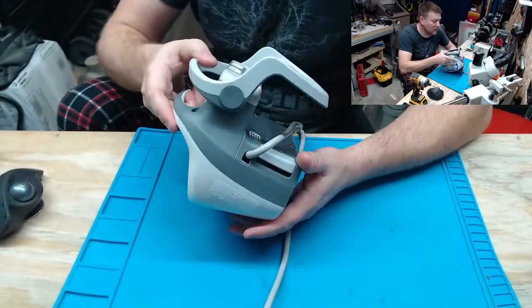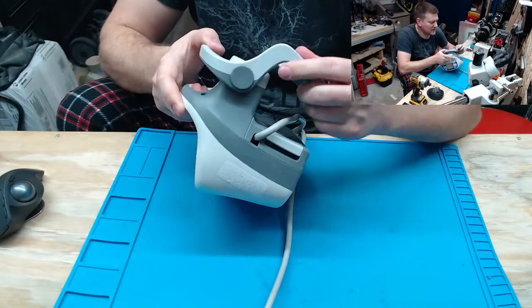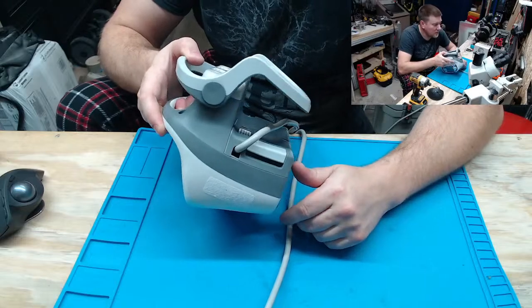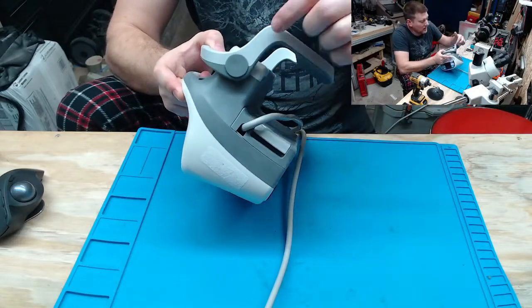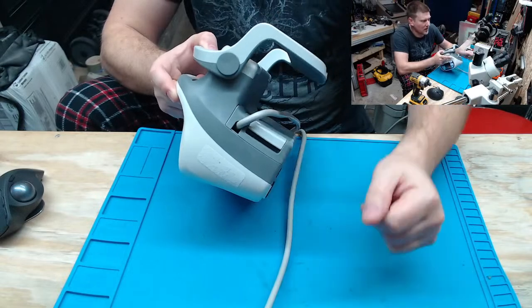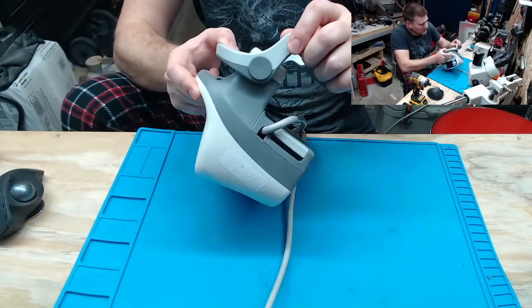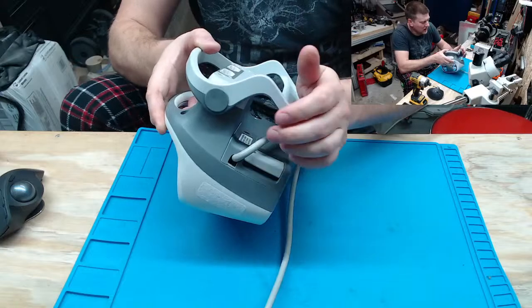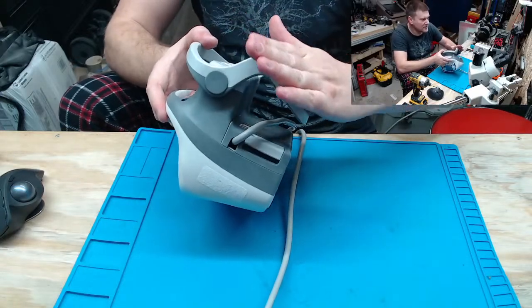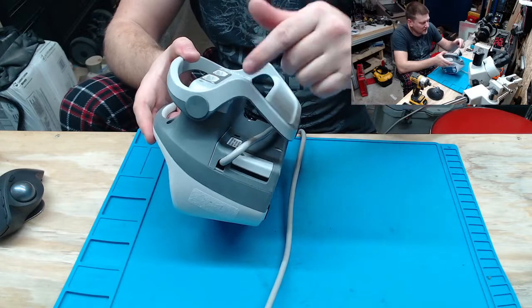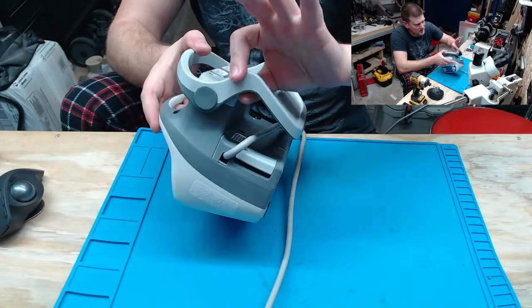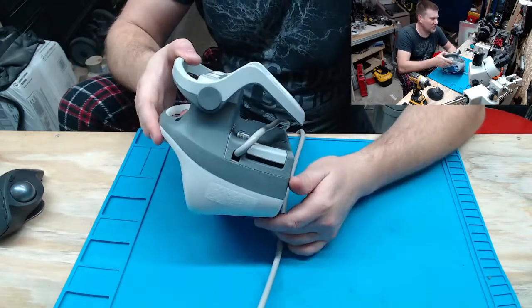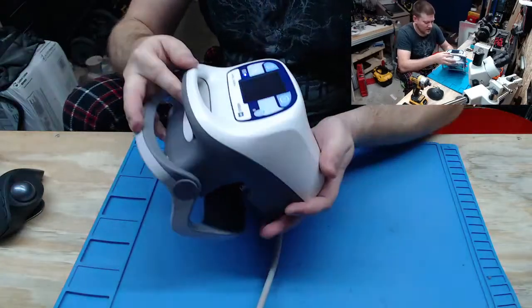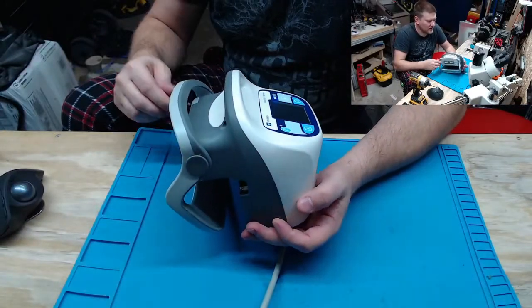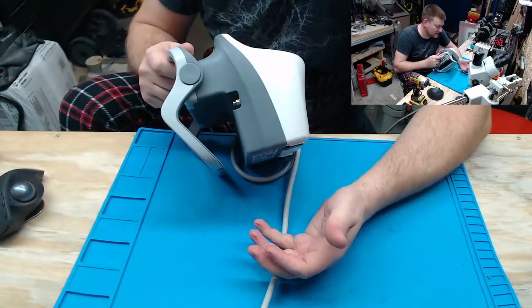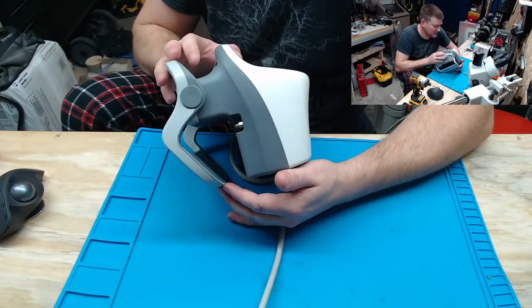Now the other thing that breaks all the time on this is this handle. In fact, I'm starting to think it's a miracle that this one isn't broken. It always breaks right here. Always. And you can see why. Even though it seems like a very durable material, it's very proud of the device. So anything that impacts it is going to hit, and all that stress is put right here on this knuckle. They always break right there. If it drops on the ground, all that stress is going to be right there on that elbow. So that's the Achilles heel of this device.